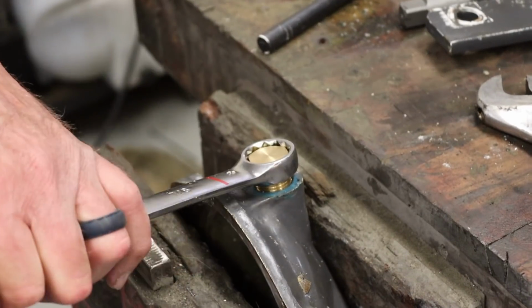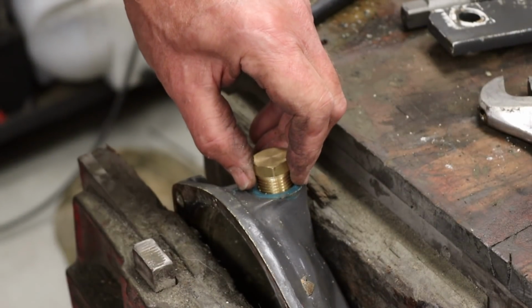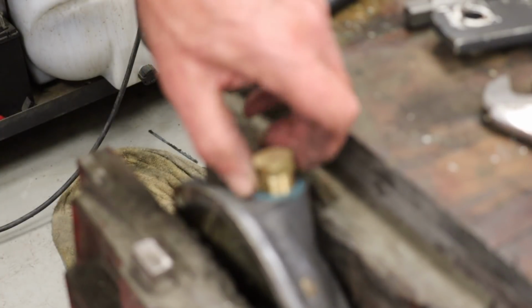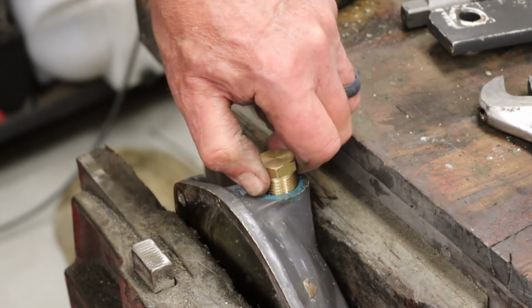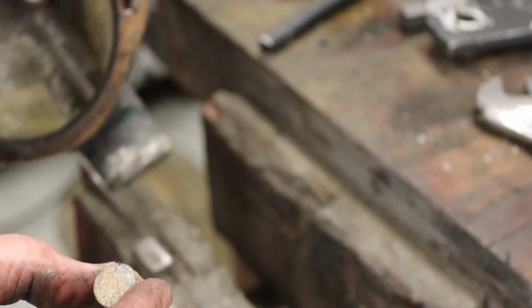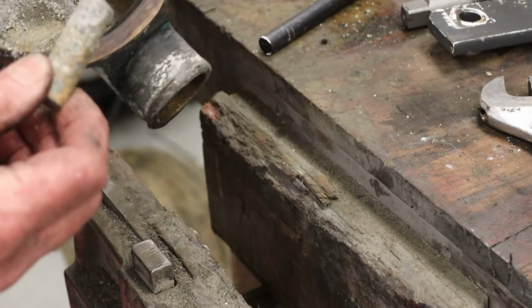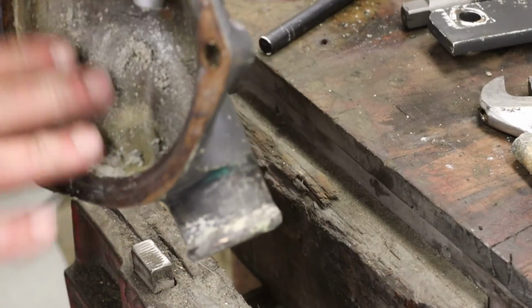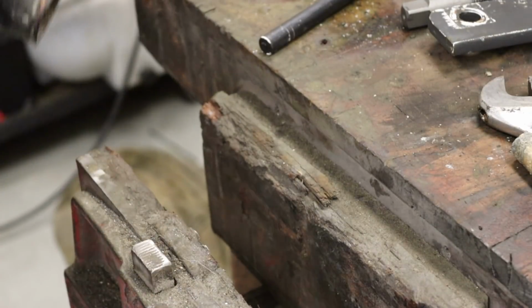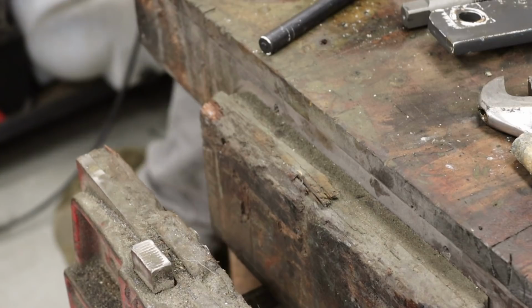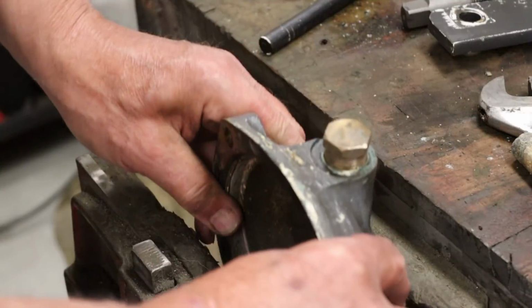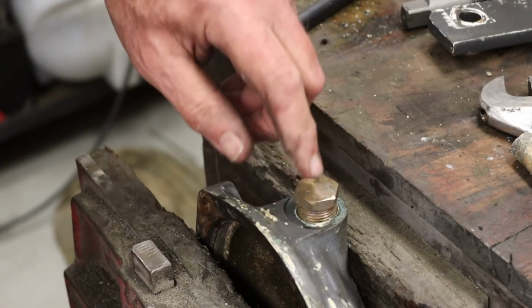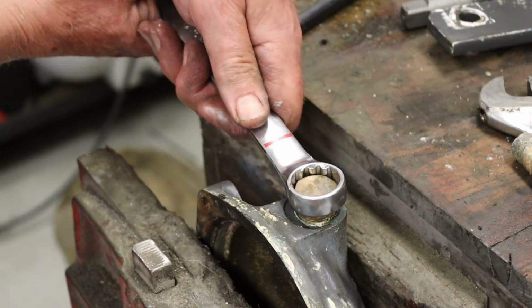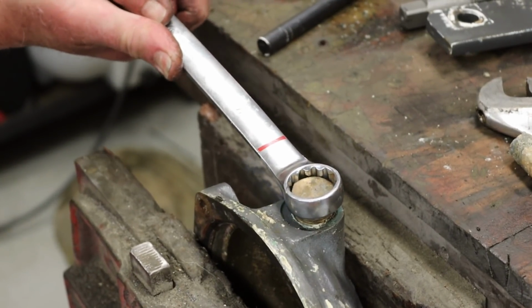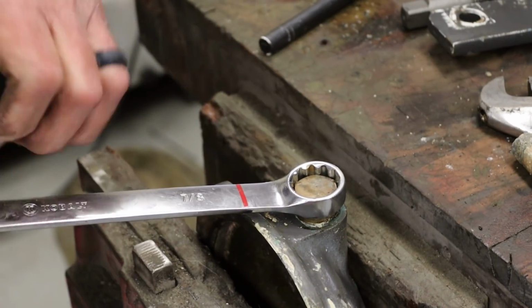You don't put anything that would interfere with the electrical connection. That's the old zinc - it's still mostly there, but it broke off. You don't want them rattling around inside the housing, though that happens from time to time. They corrode and then separate from the brass nut, and they just sit in that plenum.